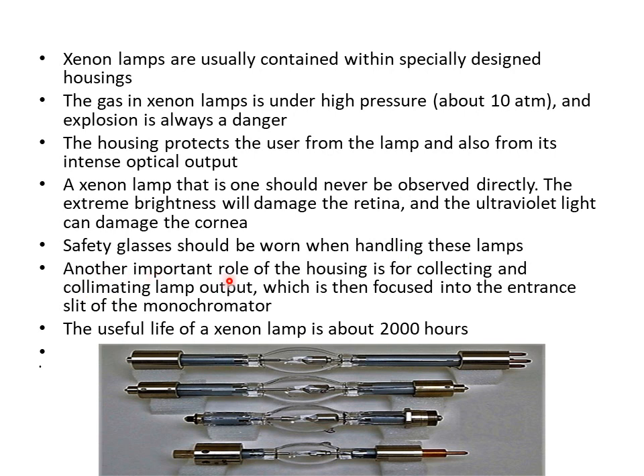Another important role of the housing is collecting and collimating the lamp output, which is then focused into the entrance slit of the monochromator. The operational life of xenon lamps is about 2000 hours.